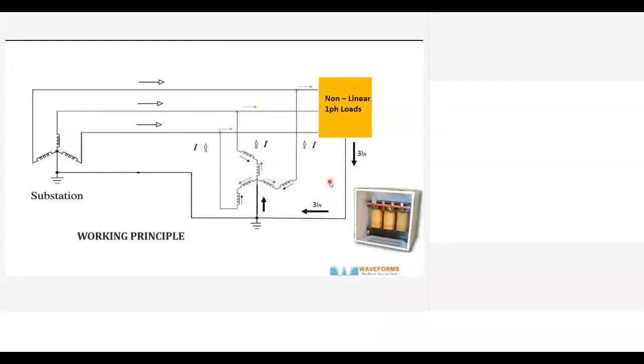So in most residential places, you will find that the transformers have a humming sound, there is heat, there is temperature, because it happens all the time in the evening or during the night. In residential places, all the lights come on and they use the TV, the music system, the computer. All this adds up. Sometimes everything can be on a single phase also, and then there can be imbalance. So you are creating a dangerous situation. So this is how it works.